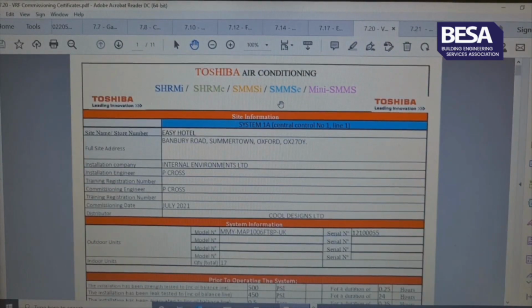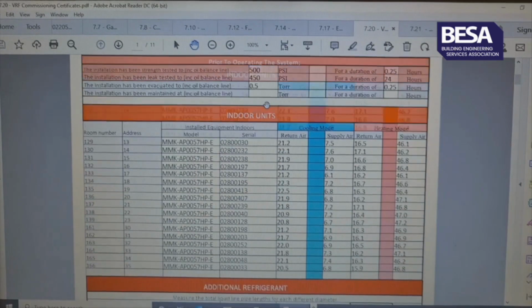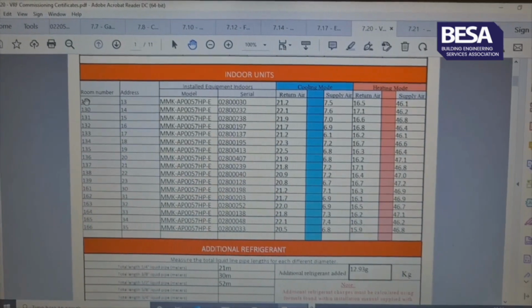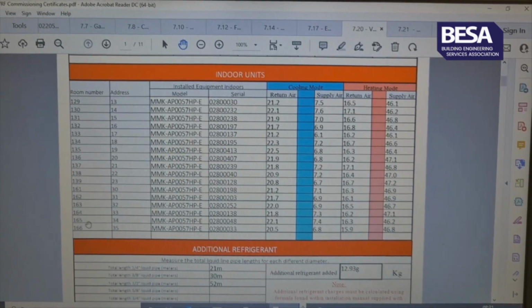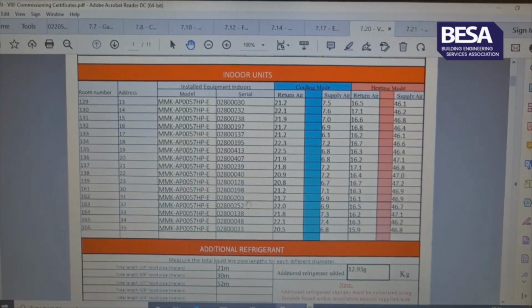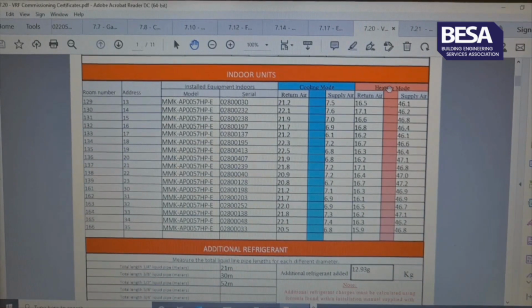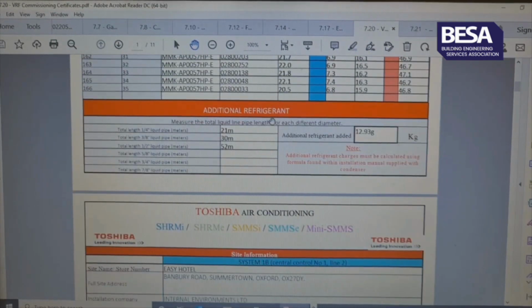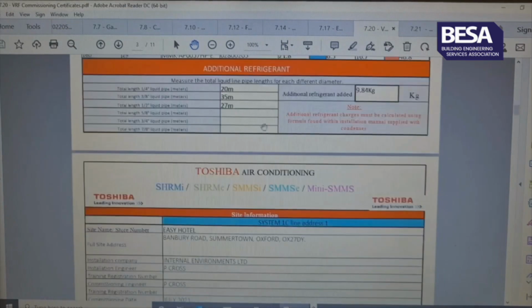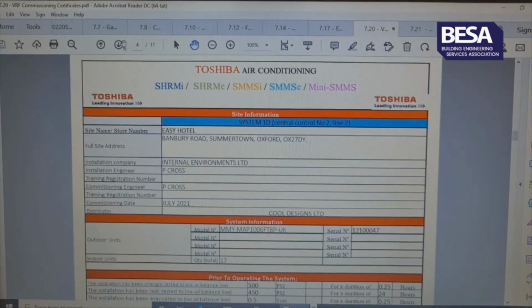This is the test certificates for the Toshiba air conditioning system, so the VRF systems that serve the hotel bedrooms. There's 10 number in total. So if we can just look at this one here, this will be one system here, all these rooms. And the model number, serial number, and in here, in both cooling and heating mode, we've got the return air temperature and the supply air temperatures. So this is what's actually been recorded on site. There's a length of pipework calculation there and a refrigerant charge, what they've added to the system. And again, it's one for every system there, so there'll be 10 in total.